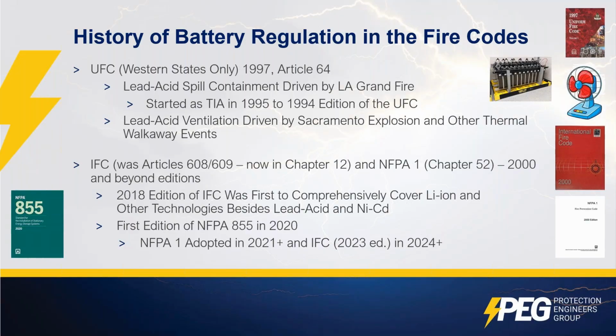Another incident that happened later was a ventilation concern and explosion at a data center in Rancho Cordova, near Sacramento. It was a data center that was essentially abandoned, but they left a UPS system with flooded batteries in position, on charge. Some of the batteries were over four years older than their recommended age, so some had internal shorts. They overcharged the batteries for several weeks. Meanwhile, the air conditioning and the ventilation were turned off. So they hydrolyzed these batteries, created a lot of hydrogen, and left the building all sealed up. Supposedly, there were reports that for several days before the explosion, neighbors could hear hydrogen sensors and alarms from outside the building, but no one said anything. And eventually the top of the building blew off.